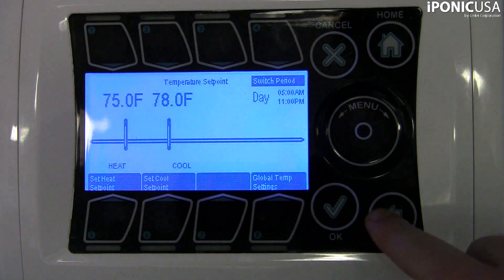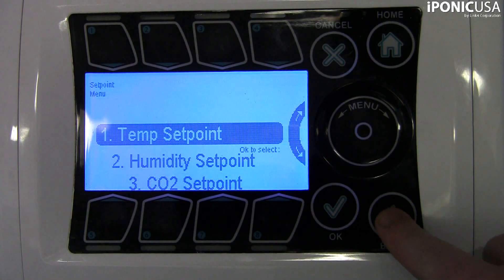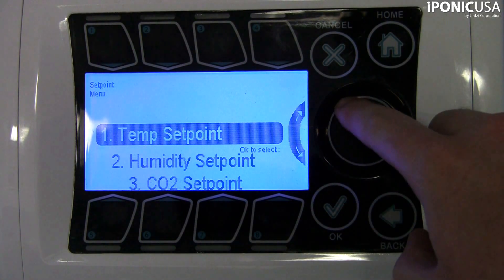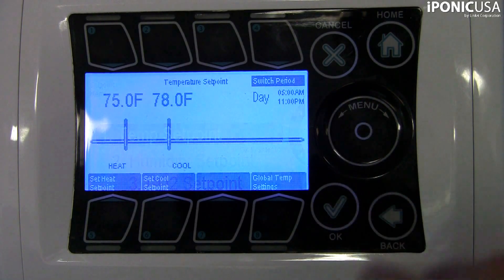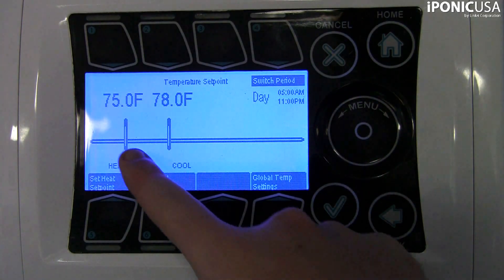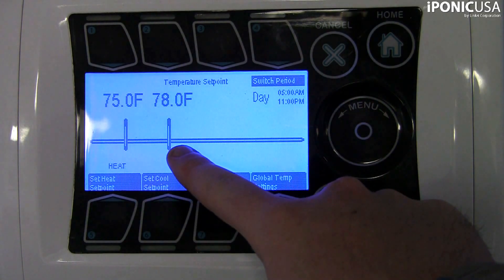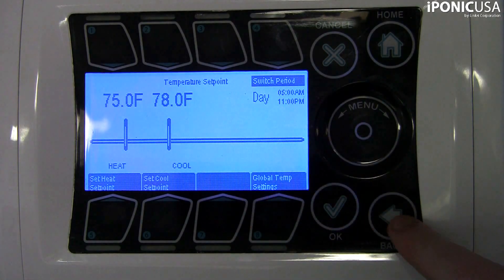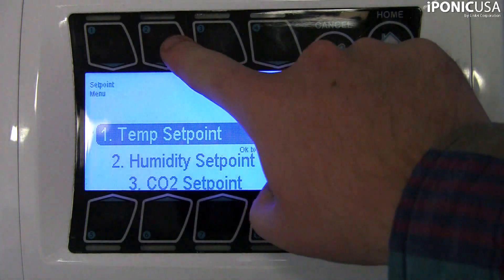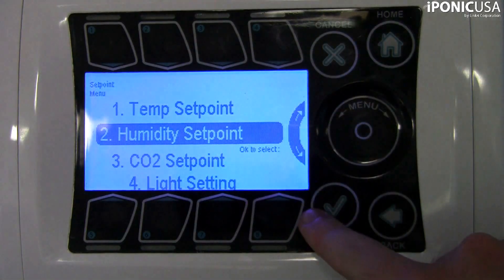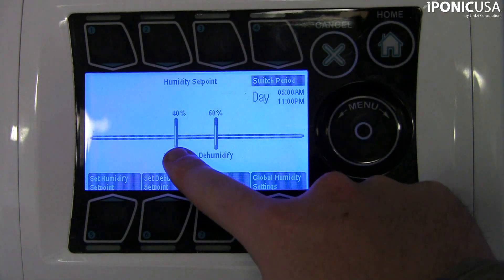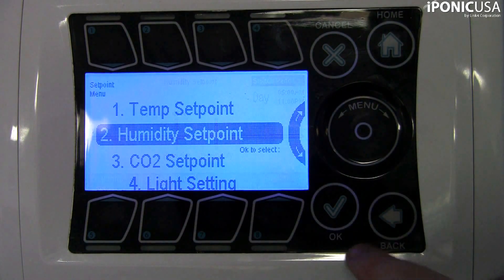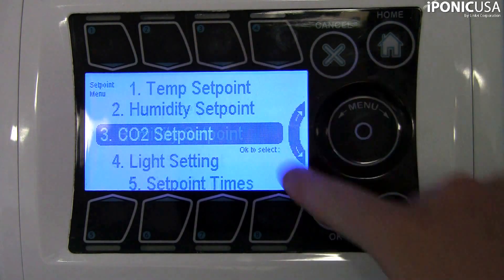The default day set point begins at 5 a.m. with a normal temperature target range between 75 and 78 degrees Fahrenheit. The humidity target range is between 40% and 60%, the CO2 target is 800 parts per million, and the lighting equipment is on to facilitate photosynthesis.